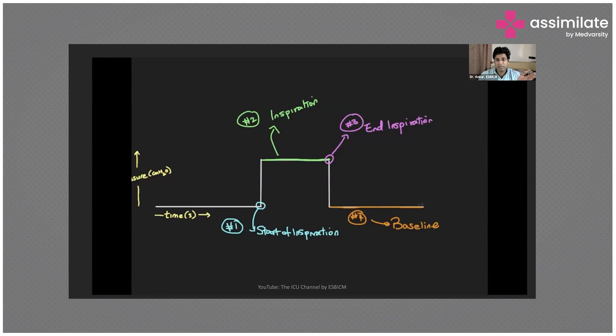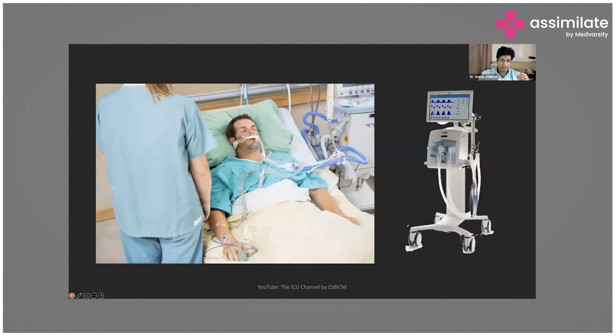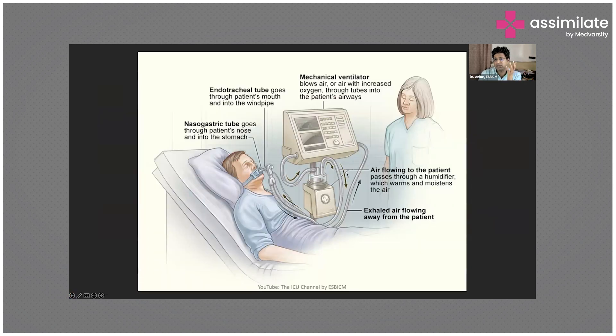For those who are new, here is how the ventilator works as a machine. At the back of the ventilator there are two or three ports — one for oxygen input and another for air input so they can be mixed properly. On the machine there are controls, a display screen with set parameters, and a graphical representation of the breath waveforms. This mechanical ventilator blows the air through an inspiratory limb going towards the patient, connected to the endotracheal tube placed in the patient's trachea.